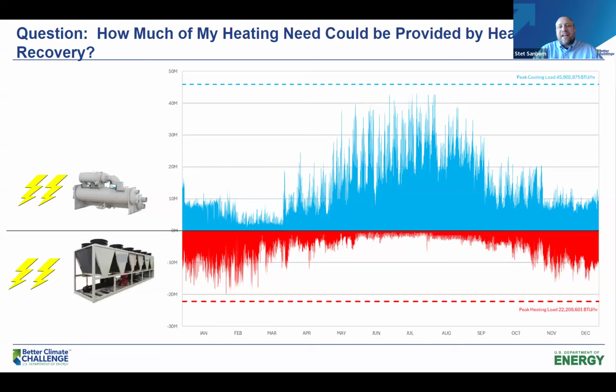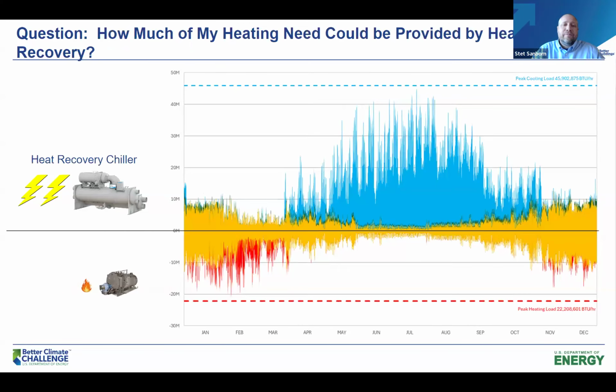And so instead of saying, just throw in a heat pump, because you'll notice if I throw in a heat pump to cover that heating load, all of a sudden I've probably doubled my electrical demand in the building. I've triggered an upgrade in the service. Those are things that I want to avoid. So instead, what if I replace my chiller with a heat recovery chiller?